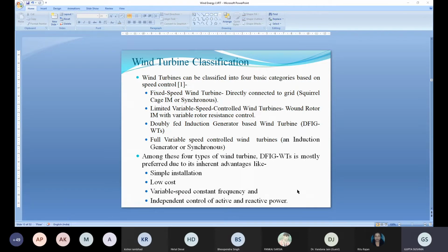So this is okay, no problem, but the problem is that they are very susceptible to grid voltage dip and disturbance, because here the stator is directly connected to the grid. So if there is a fault in the grid, the stator and the grid side converter are both influenced by the sudden change. And due to this disturbance, there is a large rotor current and a large DC link voltage. If there is a voltage dip, the rotor current will be more, and if the rotor current is more, then the DC link voltage will be more. So they can damage the winding as well as the power converter.